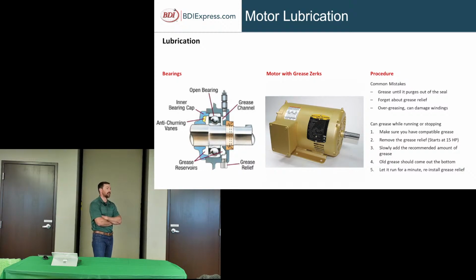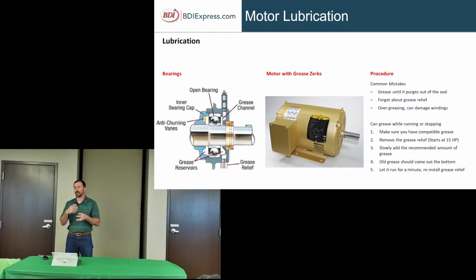If you don't see it, it could be going elsewhere. So if you keep pumping until you start seeing stuff and you're not seeing it, it could have been over greased before, or the grease relief was not removed and you now have grease in your motor. And then afterwards, let it run for a minute and reinstall the grease relief. That's going to start churning that grease and start relieving more grease. You want to get that bad grease out of there.